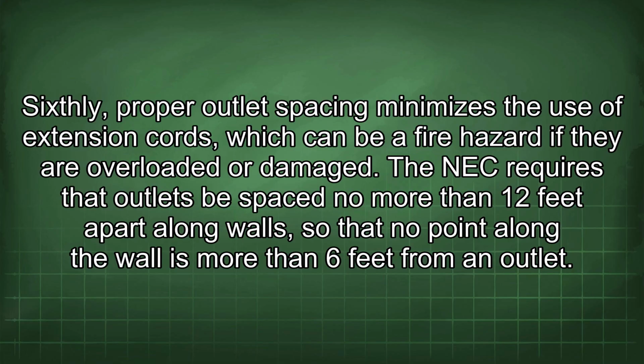Sixthly, proper outlet spacing minimizes the use of extension cords, which can be a fire hazard if they are overloaded or damaged. The NEC requires that outlets be spaced no more than 12 feet apart along walls, so that no point along the wall is more than 6 feet from an outlet.